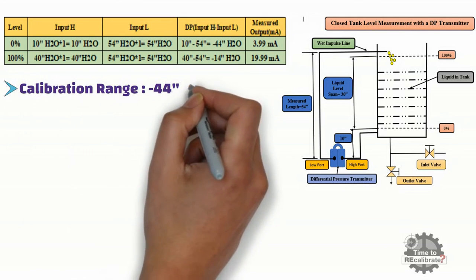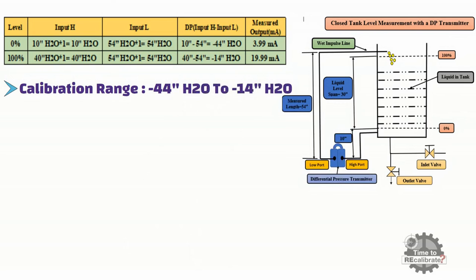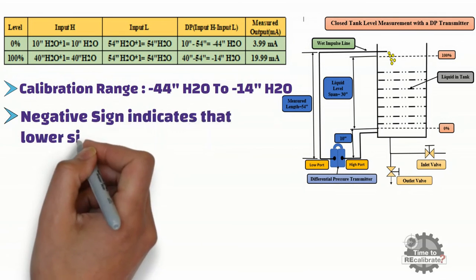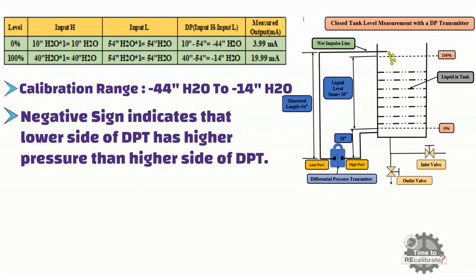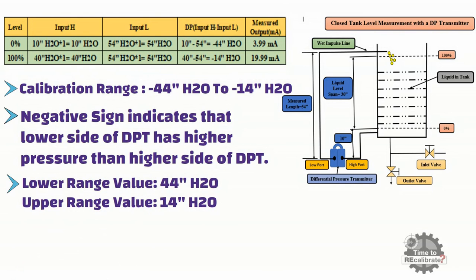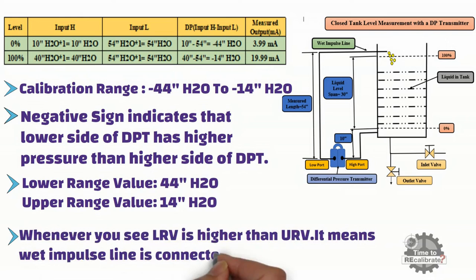As you can see from the table, the calibration range is minus 44 inches H2O to minus 14 inches H2O. Note that you will always get a negative range when measuring level in a closed tank with a wet impulse line. The negative sign indicates that the low port of the DP transmitter has higher pressure than the high port. Since you cannot set a negative calibration range in a DP transmitter, set 44 inches H2O as the lower range value and 14 inches H2O as the upper range value. Whenever the lower range value is higher than the upper range value, it means a wet impulse line is connected to the low port.